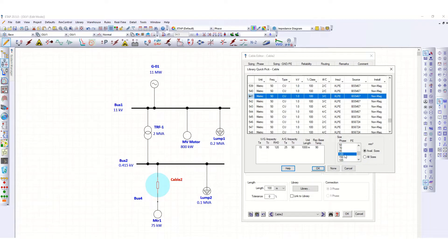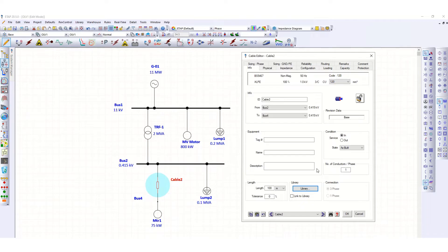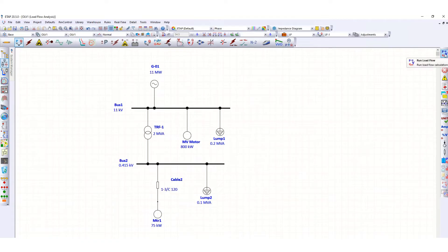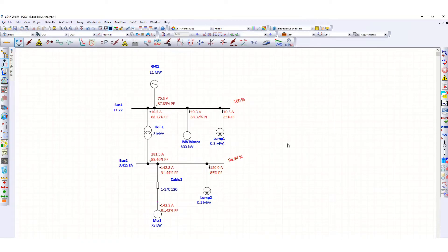This is preliminary data I am giving, and later I will size the cable using the software's ampacity calculation. Click OK. Now let's check the current passing through this cable to the motor by running the load flow analysis. You can see 142.3 ampere current is being drawn.